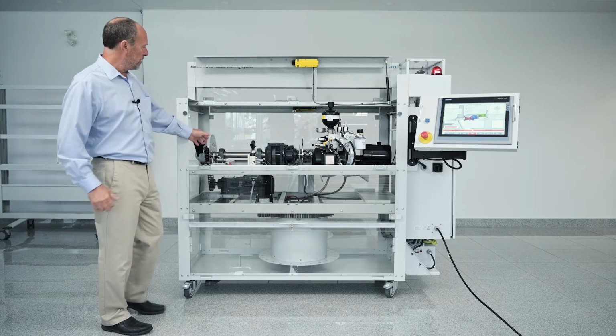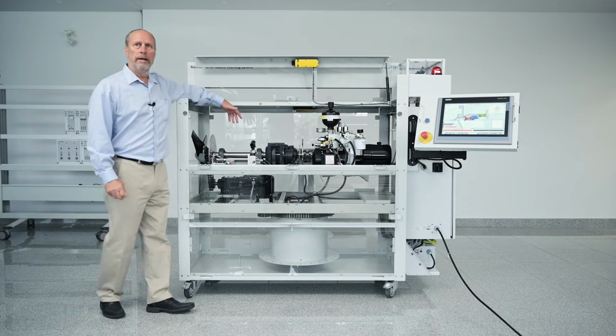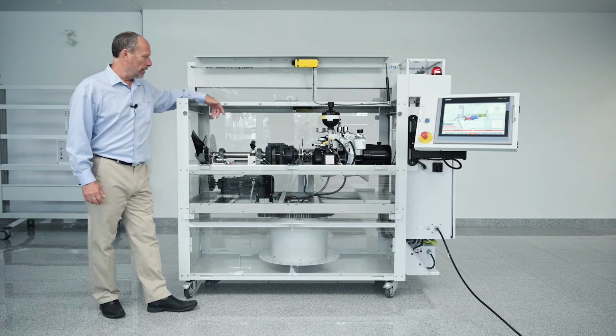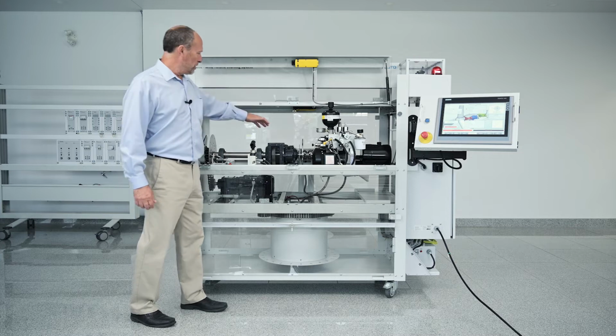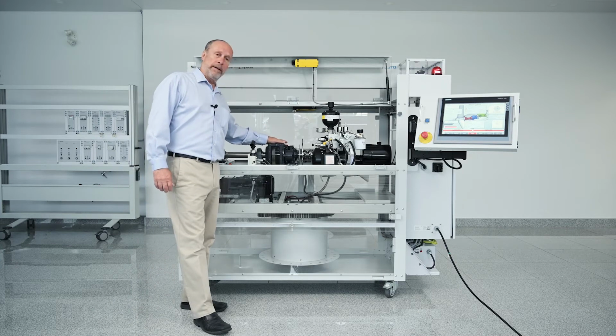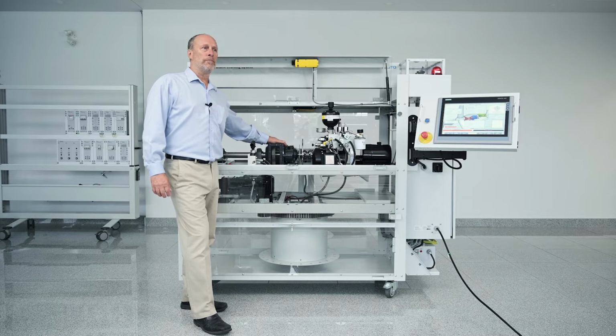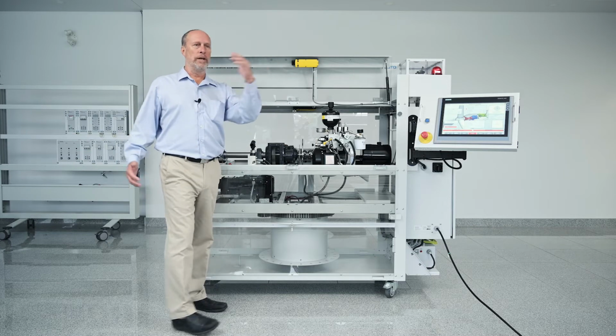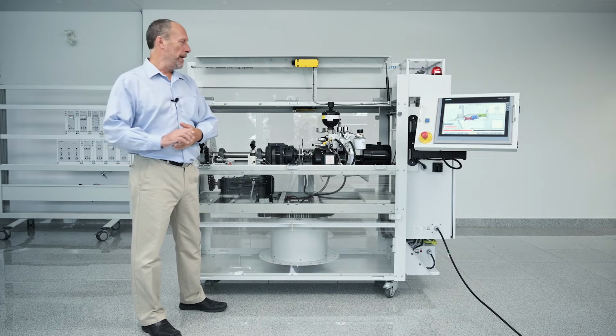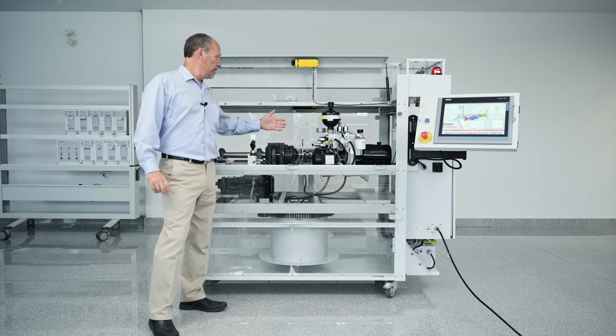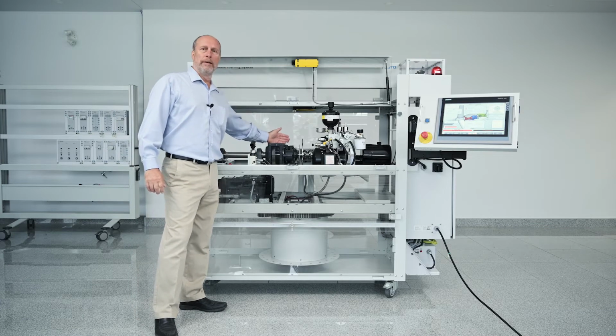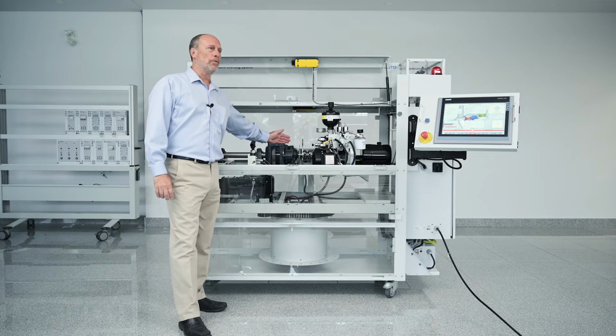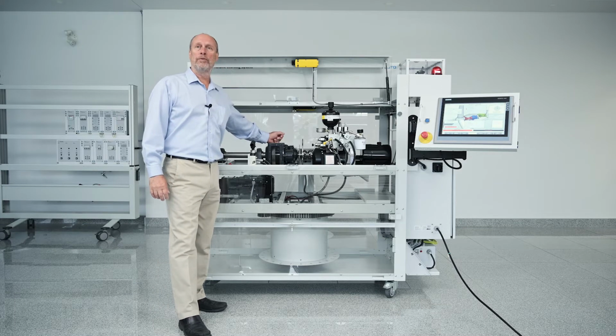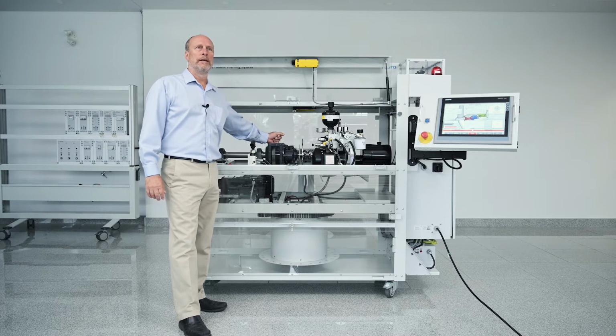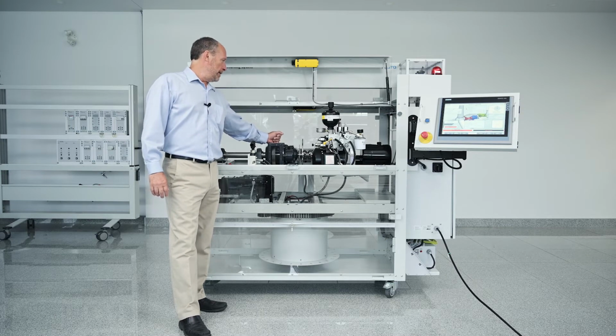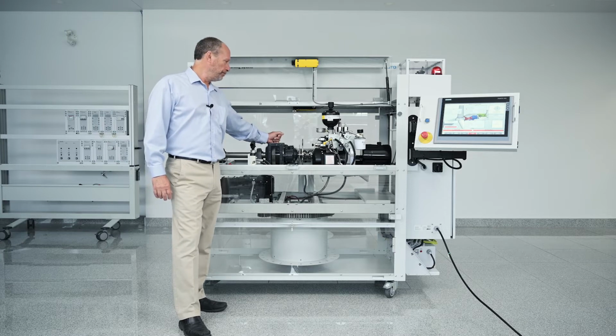So here the main shaft with the big pillow blocks. This is the main part of the internal of the nacelle. For speed adaptation, we have here a gearbox. So for those machines that run at 20-25 RPM, the blades at that speed is not enough. So there's a gearbox to bring the generator to speed. So we're looking at 1500 RPM for the 50 Hertz and 1800 for the 60 Hertz.